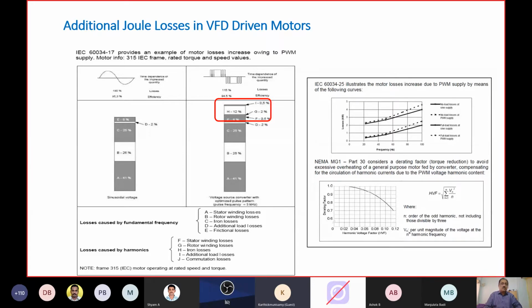34-2-2, if I'm not mistaken, or 2-3, is the standard now for testing VFD plus motor. So there is no more classification of IE3 becoming IE2 when used with a VFD, or IE2 becoming IE1. That is not valid any longer. And I think some of the leading manufacturers in India have also adopted it.